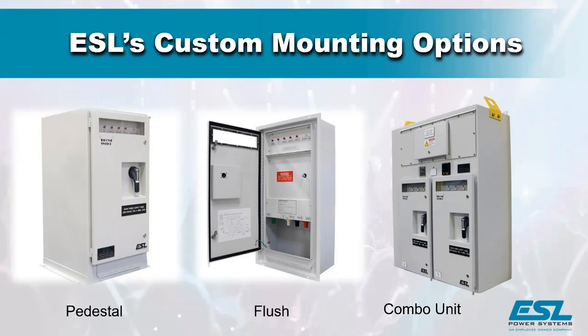I know sometimes cam switches will have dummy plugs in the bottom of them, so you plug in the dummy plug to tell the cam switch that there's a plug in that particular cam. But that's used almost exclusively when the cams are on the outside of the unit, since there's a danger of having an exposed cam. In our case, all the cams are inside the chamber and completely safe.